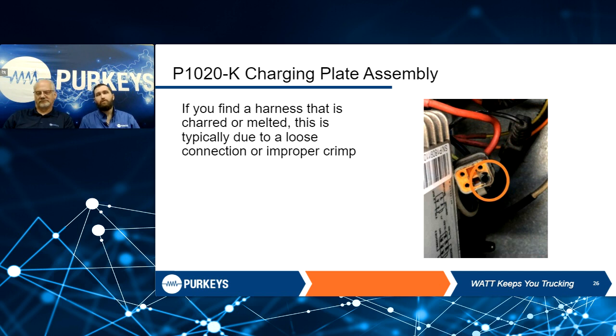That's usually due to an improper crimp or a loose connection on one of those pins. So if you suspect that something may be loose or that you're generating a lot of heat and you haven't reached this point yet, it's always good to pull out that orange plastic insert and make sure all your pins are locked in. Once you've verified that, go ahead and reinsert that plastic insert, plug it back in, and see how your results fare from there.